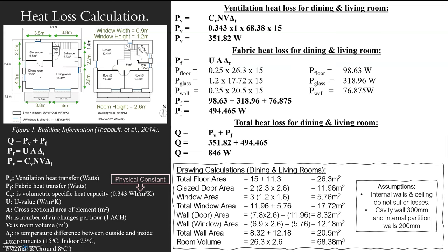When we get to ventilation, we need to know the heat capacity of air, because if you're transferring air in and out of a room, you need to know how much heat is transferring in that air. That value is a physical constant — standard air is 0.343. I've written that there.